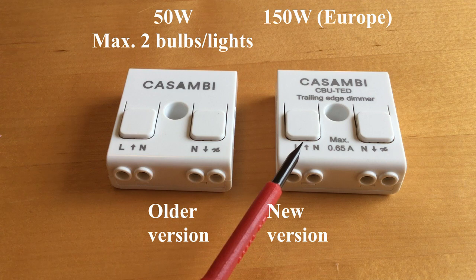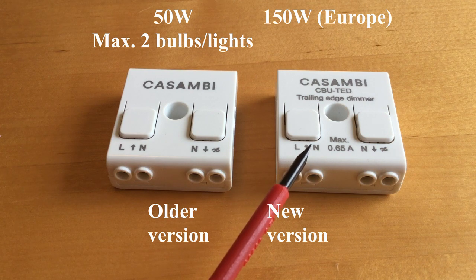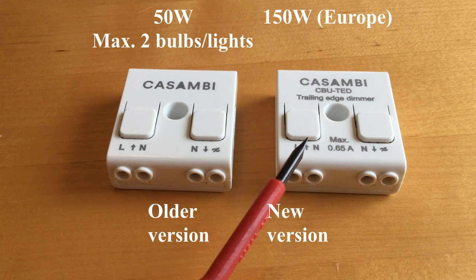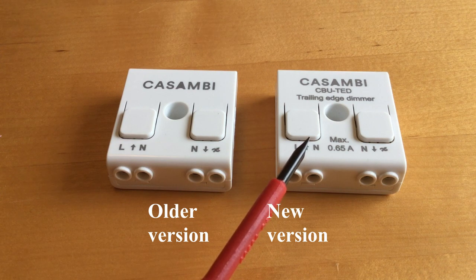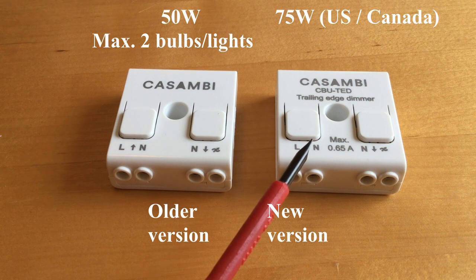The new one is available in the US or Northern America and in Europe. There are two different variants for the new version. In Europe, it can output up to 150 watts, and there are no limitations as to how many luminaires can be attached to a single TED, but you do need to bear in mind the inrush current. See more about that at the installation guide on Casambi's website. For the US market, it can output up to 75 watts. So again, 150 watts in Europe, 75 watts in Northern America.